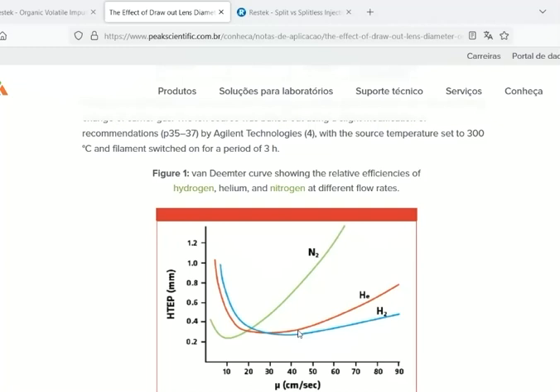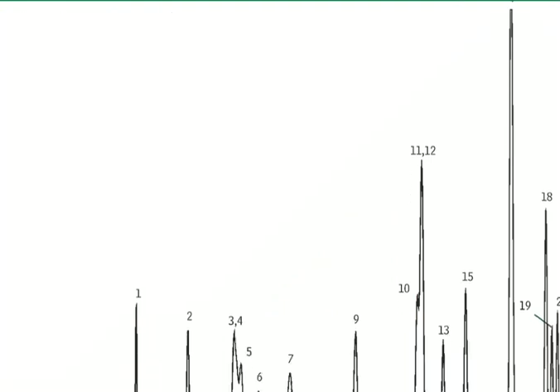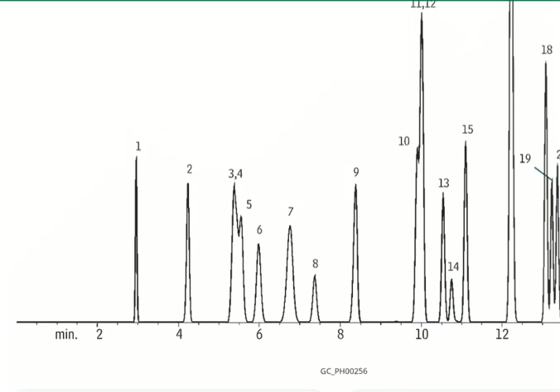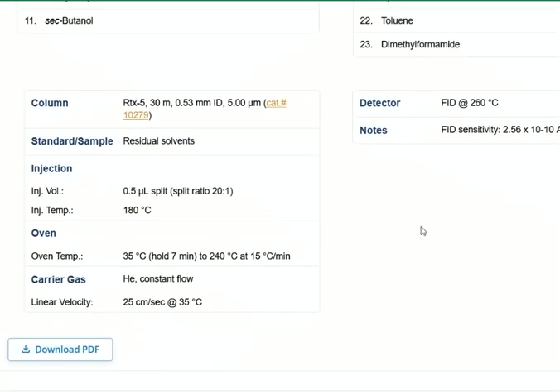Next we're going to look at a method and then transfer that method into the software. Here is a method for organic volatile impurities on an RTX-5 column. There's the chromatogram and all the different peaks. Here is how it's presented to us: first you have the column type, injection volume, split ratio, injector temperature, oven temperature with the oven temperature profile, the carrier gas, carrier gas linear velocity, and the FID temperature. We're going to take these values and transfer them into the software.